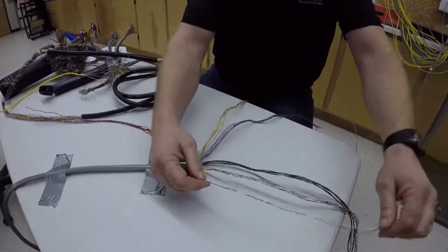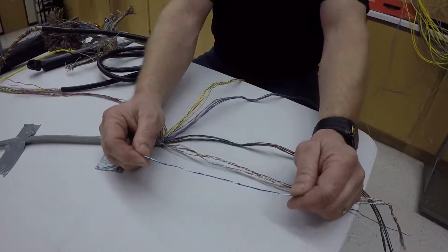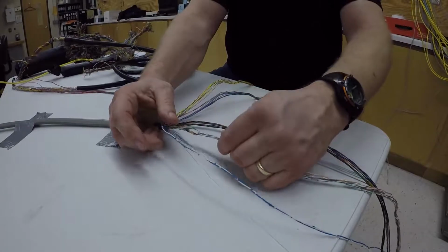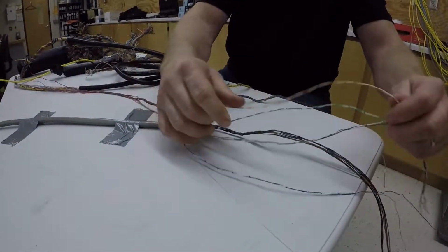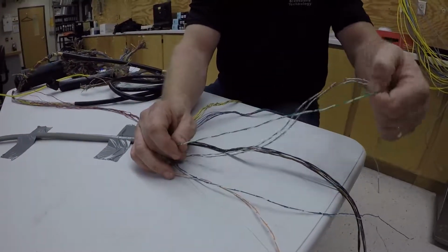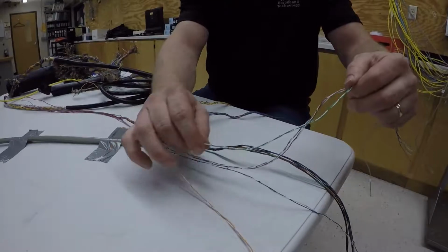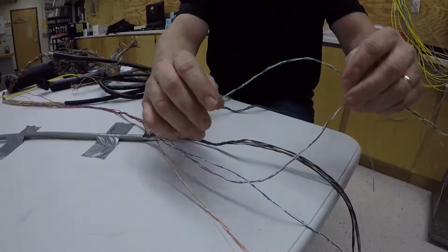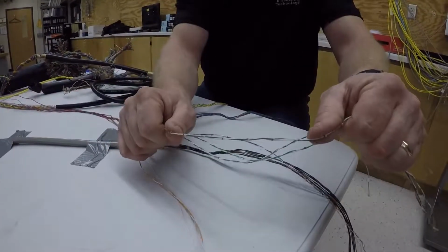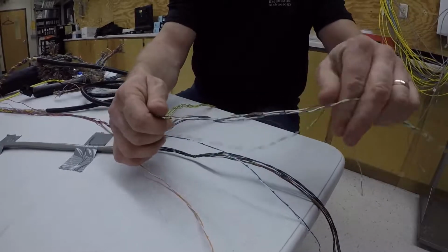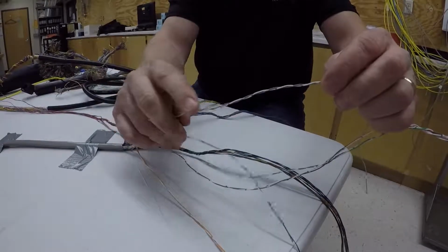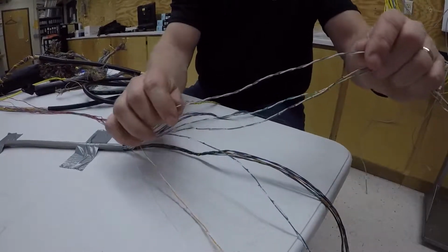So pair number 1, of this plastic insulated color, is white, blue, blue, white. That's pair 1. Pair 2 is the white, orange, orange, white. Pair 3 is the white, green, and green, white. And you can see the different colors for identifying these cables. Pair 4 is the white, brown, and brown, white. And pair 5 is the white and slate. We don't call it gray, it looks gray, but in the industry it's called slate.